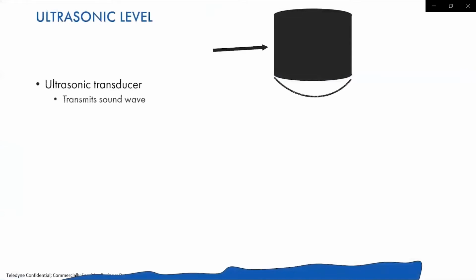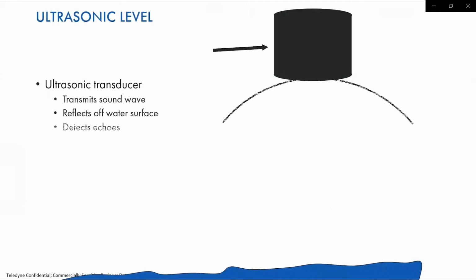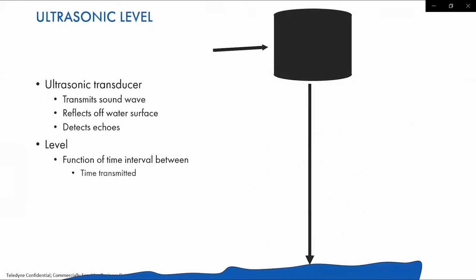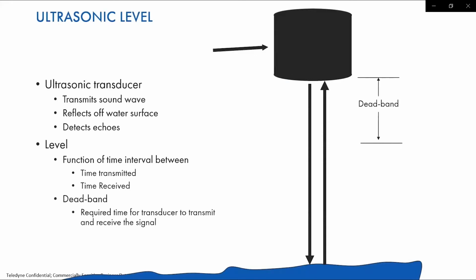Some of you have seen this before. An ultrasonic sensor transmits a sound wave, reflects off the surface of the water, and detects the return echo, which is a function of time between the transmit and the receive signal. Now, all ultrasonic sensors have a deadband, and the reason is because the sensor needs a certain amount of time to be able to transmit that signal and then get the return signal back.